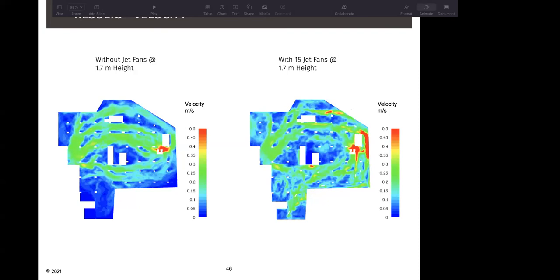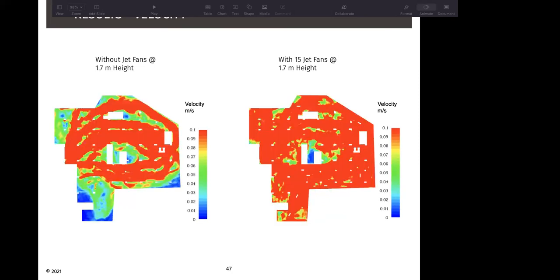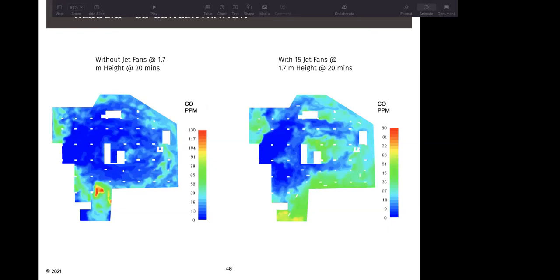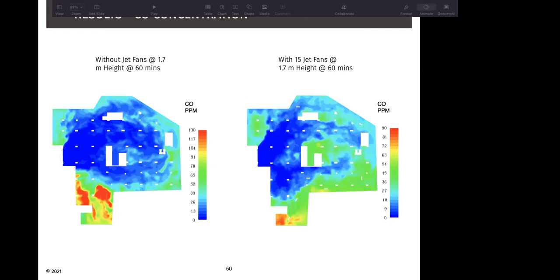So now again, going through the process, first we look at the velocity contours. We see that there are quite a few zones which are underventilated and are stagnant, especially in the lower side of the car park. Adjusting the scale to 0.1 meters per second, there are quite a few underventilated and stagnant zones, and especially again in the lower side of the car park. Now looking at the CO contours for the same, what we see is that the CO for 1 hour exposure goes to 130 ppm in that lower side where there was a stagnant zone without jet fans. And with 15 jet fans, that CO remains at 90 ppm. Now, as per ISHRAE, we consider an average of 35 ppm for 1 hour exposure with a peak of 120 ppm. So in terms of ppm, without jet fans, this basement car park is not within the acceptance criteria.